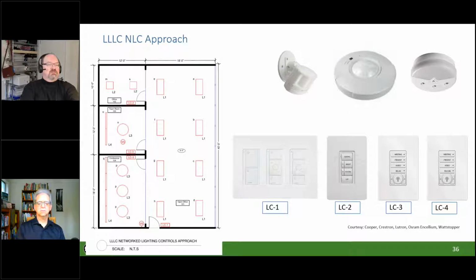Let me give you a quick example. I showed you the TechX office earlier, where we had a daylight control zone, primary and secondary, and a variety of other places. From a design standpoint, I'd have to decide exactly how to configure these rooms beforehand so the wiring between individual light fixtures would be done correctly. But what if I want more flexibility, or the ability to change over time—maybe add a demountable partition and turn an open office into several private offices? With a network lighting control system, I'd likely need to do some rewiring. With the LLLC approach, I just have some programming to do, because each light fixture is individually addressable and has its own sensors. So in a lot of ways, it simplifies the upfront work.